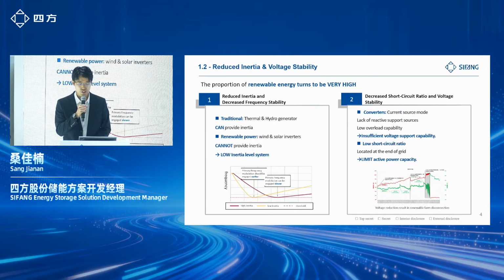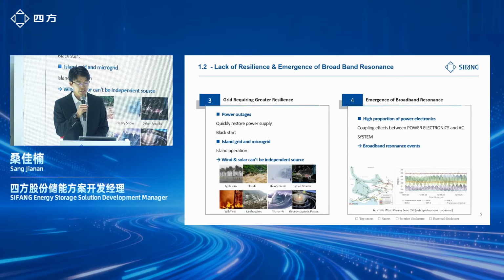A low inertia system is also limited in active power, right? The second problem is decreased short circuit ratio and voltage stability. The third is greater resilience. We all know that wind and solar cannot be an independent source, so island grids and microgrids all need to adopt grid-forming technologies. The last one is broadband resonance, coming from the power electronic devices and the AC coupled system.